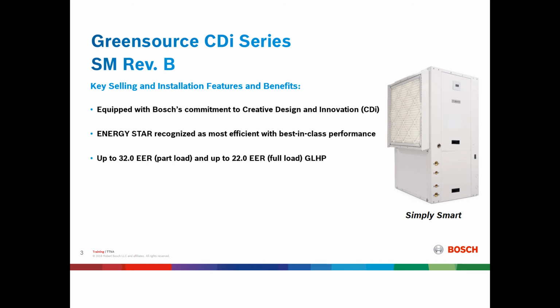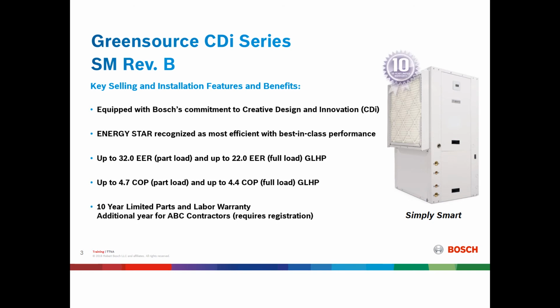The unit offers up to 32 EER part-load cooling performance and up to 22 EER full-load cooling performance. Additionally, the SM Rev B offers up to a 4.7 COP at part-load heating performance and up to a 4.4 COP at full-load heating performance. Finally, one of the best benefits offered with the Bosch SMB unit is the 10-year limited parts and labor warranty. And if the installing contractor is a member of our Accredited Bosch Contractor Program, or ABC, the customer will receive an additional year of warranty coverage if the installation is registered with Bosch.